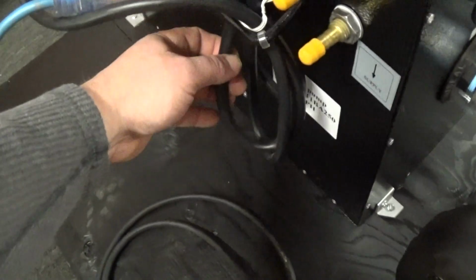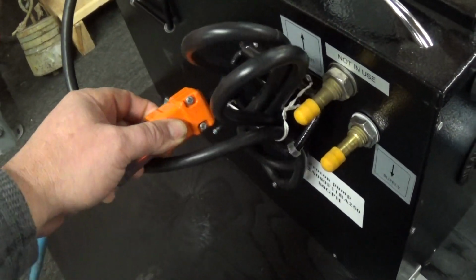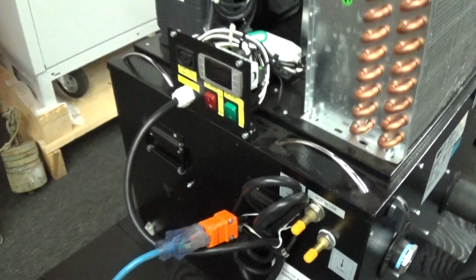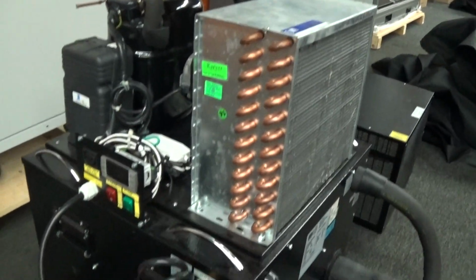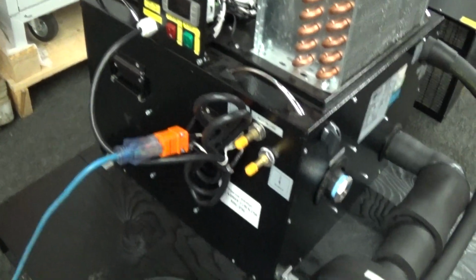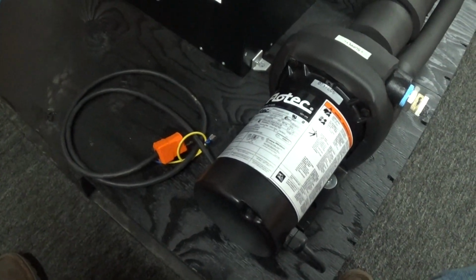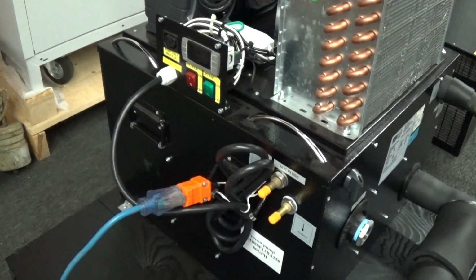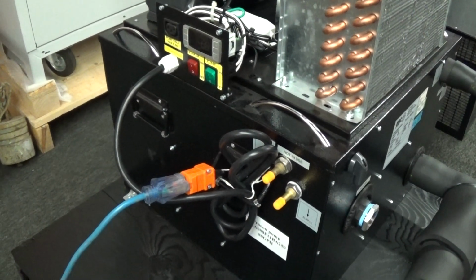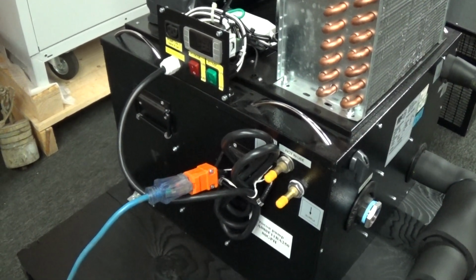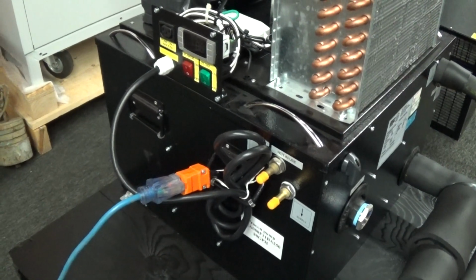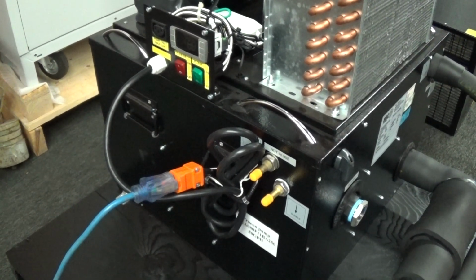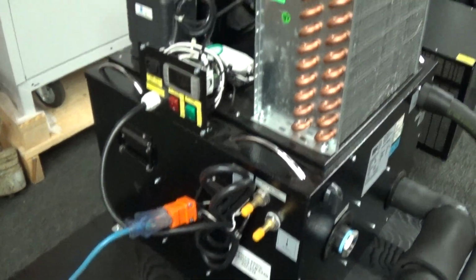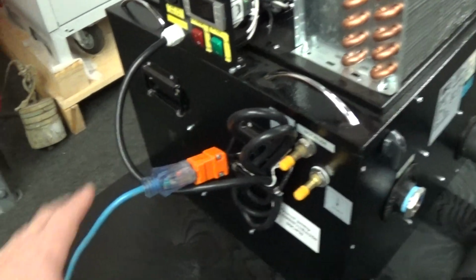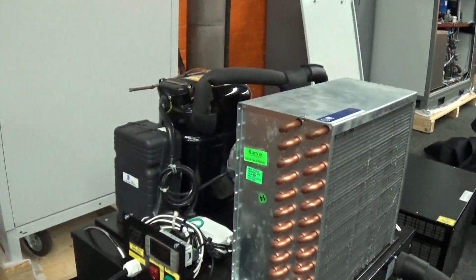The second is the power cord here, which is another 115 volt plug. That's for the main compressor and condenser portion of your chiller. The pump should be on its own circuit, 15 amp. The compressor condenser combination should be on a 15 amp circuit, unless you think it's going to get hot in your building environment. And by hot I mean over 95 Fahrenheit, in which case it'll put more load on the unit.